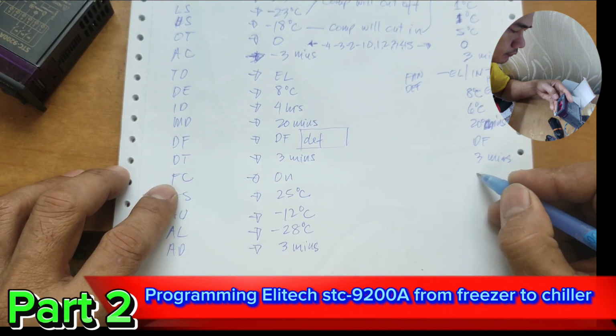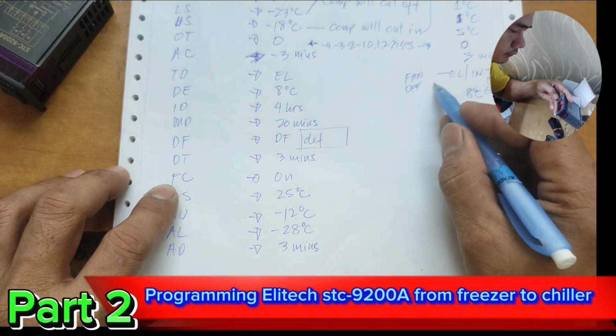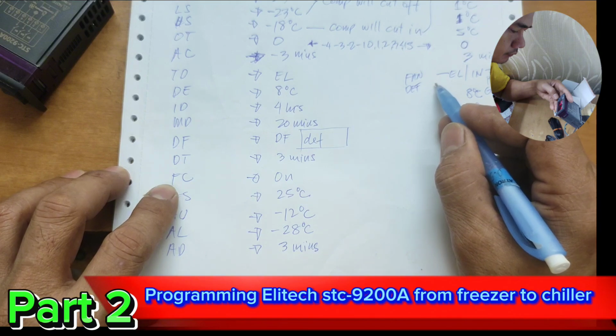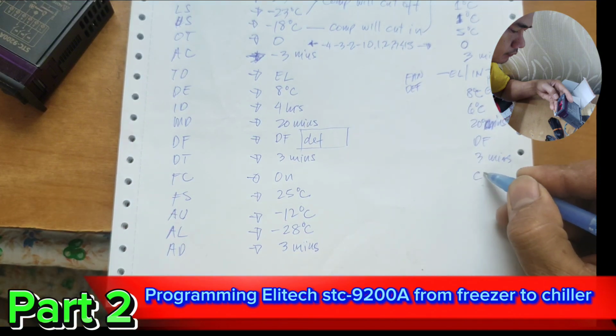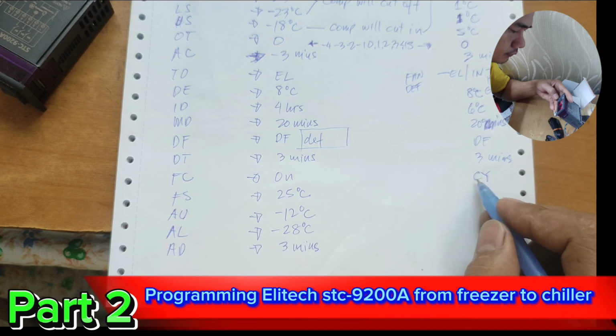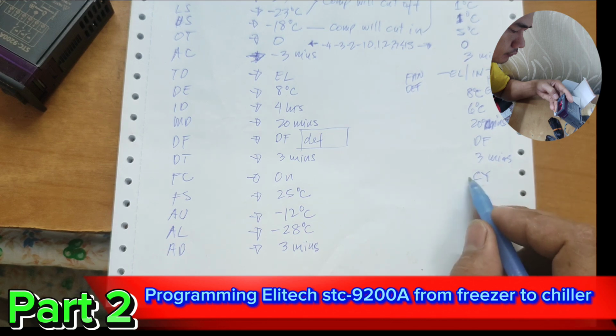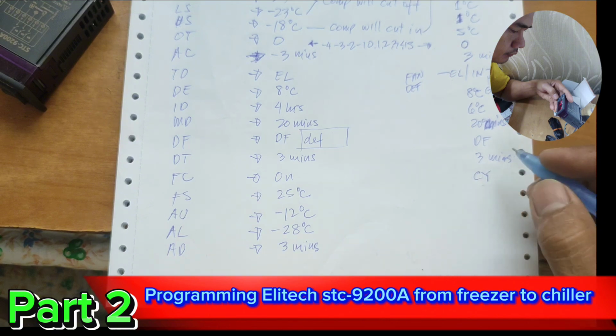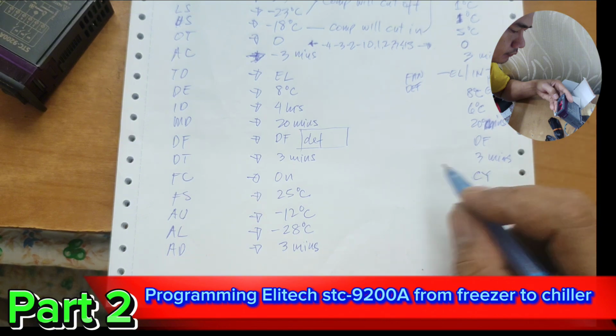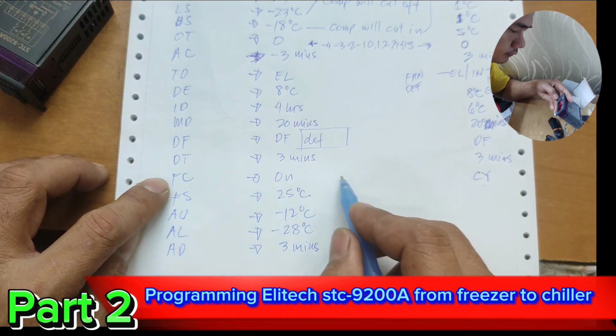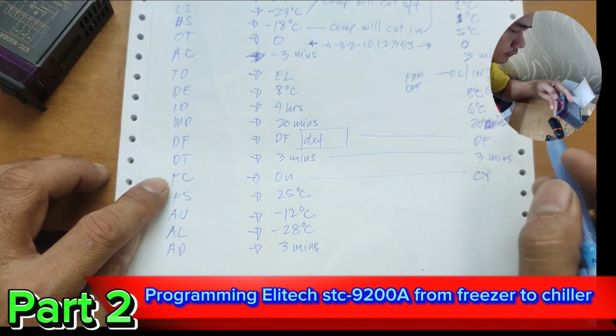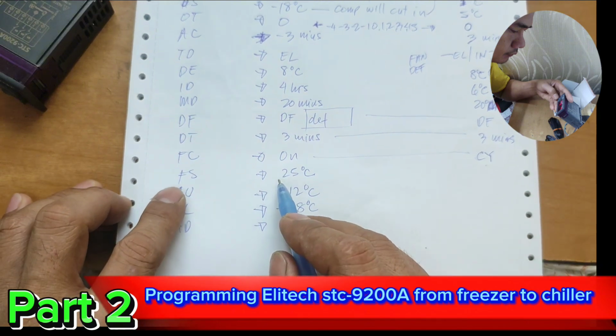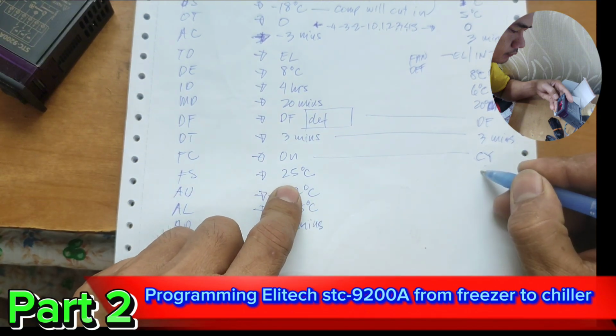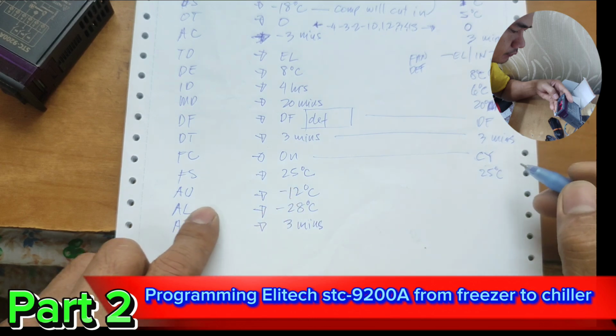For the FC, just select, if you are in fan defrosting, you should choose CY, evaporator fan runs with compressor on during defrost. Take note, guys, you should choose CY for FC. And then for fan stop temperature, same, use 25 degrees Celsius.